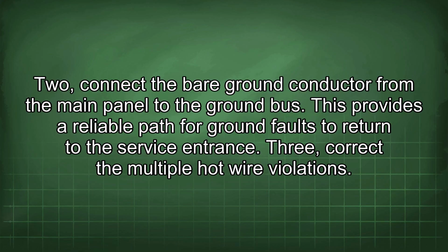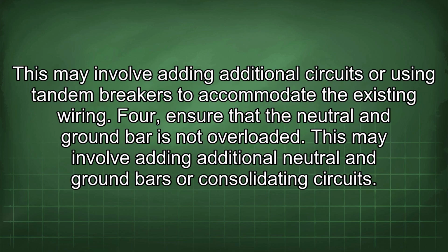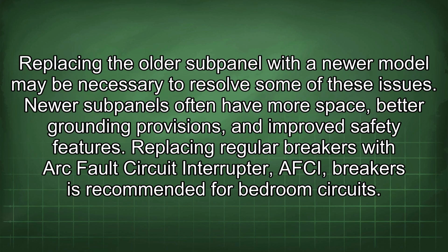3. Correct the multiple hot wire violations. This may involve adding additional circuits or using tandem breakers to accommodate the existing wiring. 4. Ensure that the neutral and ground bar is not overloaded. This may involve adding additional neutral and ground bars or consolidating circuits. Replacing the older subpanel with a newer model may be necessary to resolve some of these issues. Newer subpanels often have more space, better grounding provisions, and improved safety features.